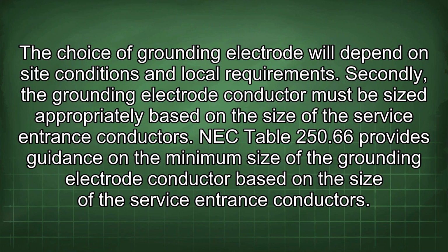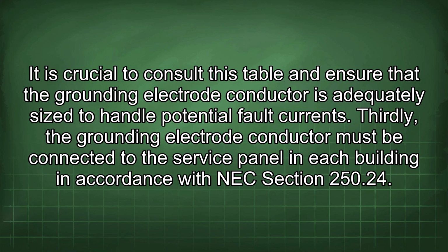Secondly, the grounding electrode conductor must be sized appropriately based on the size of the service entrance conductors. NEC Table 250.66 provides guidance on the minimum size of the grounding electrode conductor based on the size of the service entrance conductors.